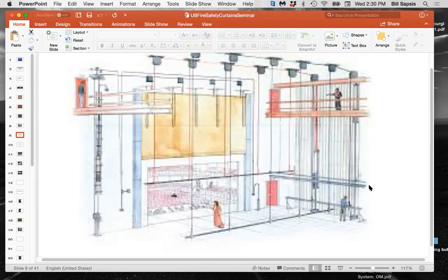So smoke doors exist. You should inspect them frequently to make sure that visually it appears that they are working. Put somebody up on the roof every once in a while to make sure that nothing has happened to impair their operation. There have been times when a theater will have a new roof put on, and the roofing contractor doesn't know anything about smoke doors, and they put the flashing right up to the side of the smoke door and tar it all over, and there's not a snowball's chance in hell that that door is ever going to open.